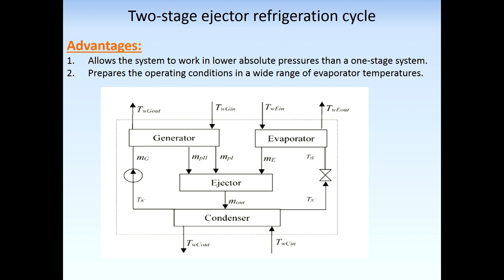The idea here is to use a two-stage ejector for the refrigeration cycle. Unlike common models, this does not mean using two separate ejectors in parallel or series. Instead, an unconventional model is used in which the ejectors are merged into one structure. In the two-stage ejector, the first stage ejector has no diffuser and is connected directly from its constant diameter section to the second ejector.